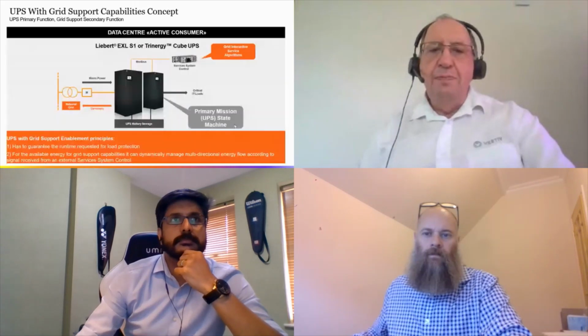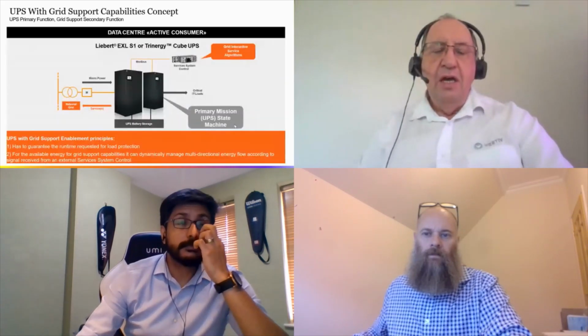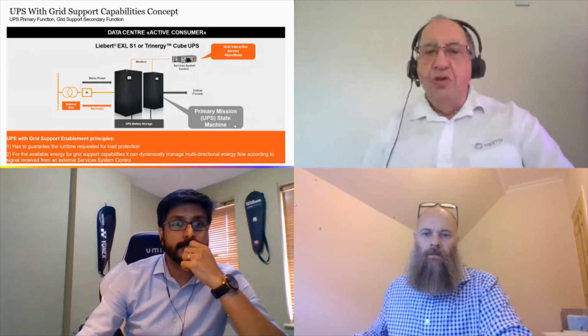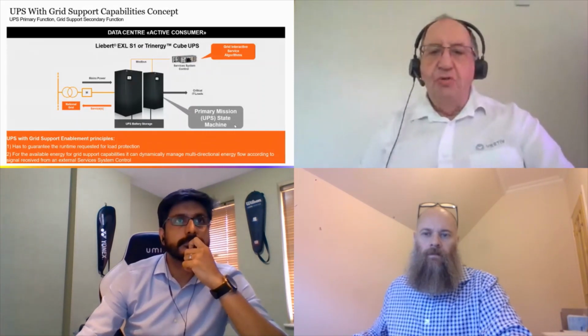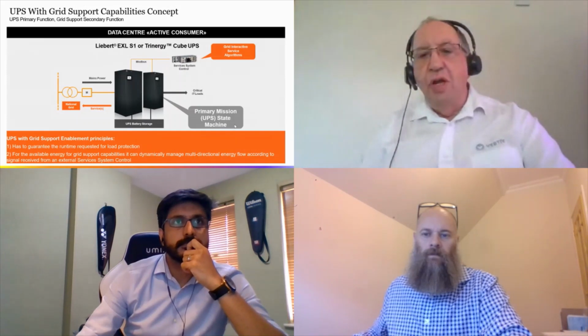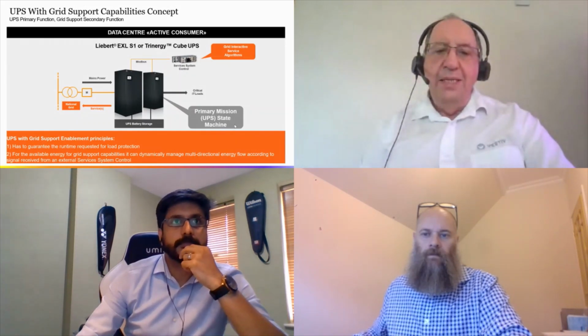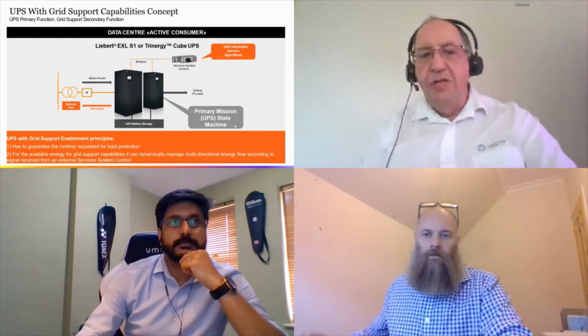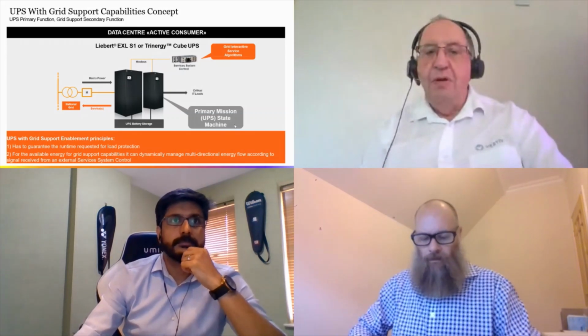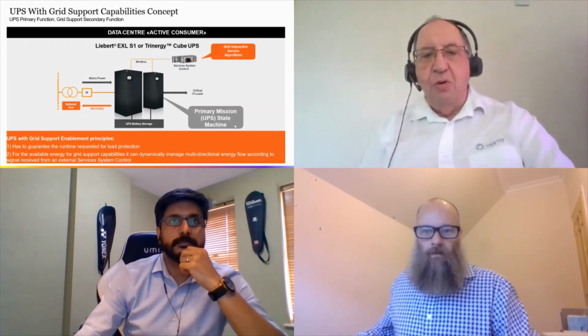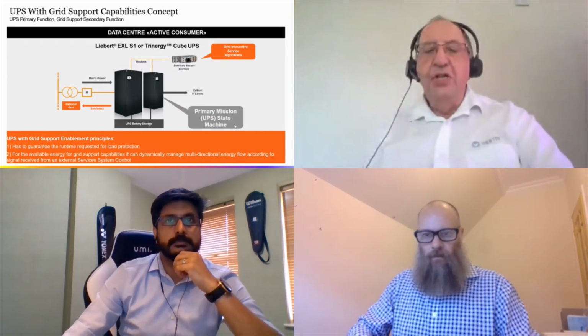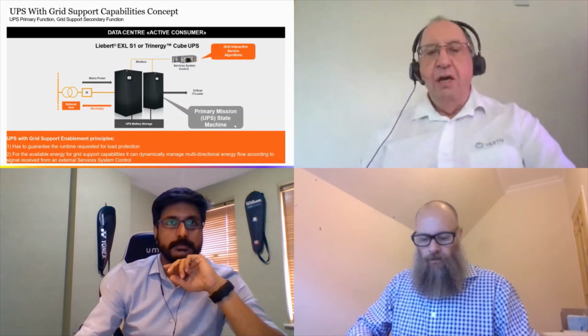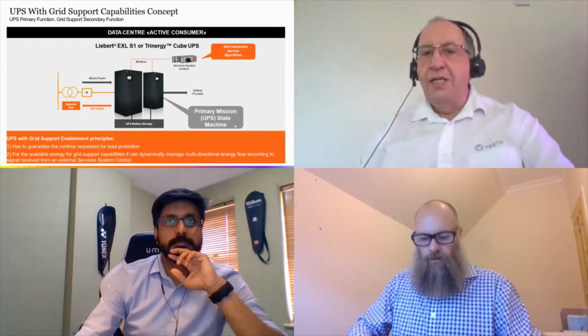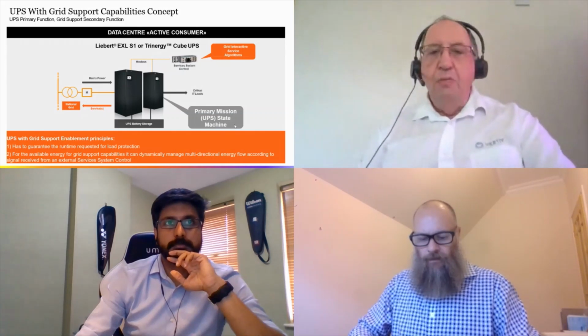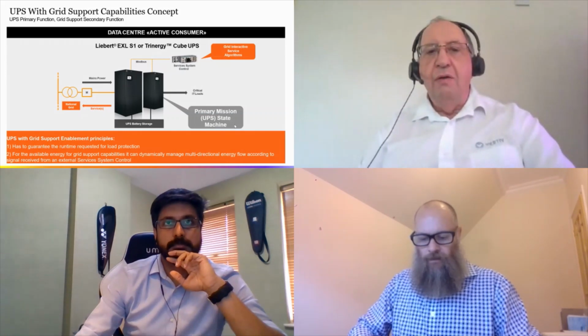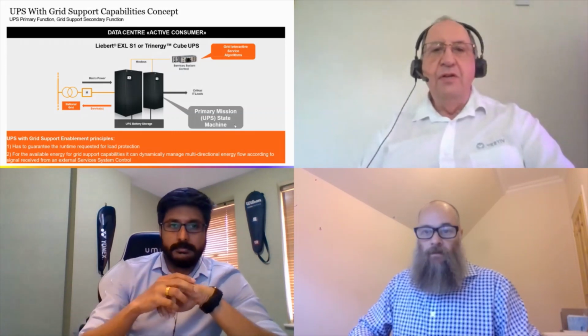Our system is basically a standard UPS with a control system, with a battery storage system, and then the critical loads downstream, but with the ability to export and keep the critical loads supplied at the same time. And it's quite a clever algorithm that manages this. And if you've got a modern UPS, then it could be possible to do this with several vendors in the industry as well as Vertiv.